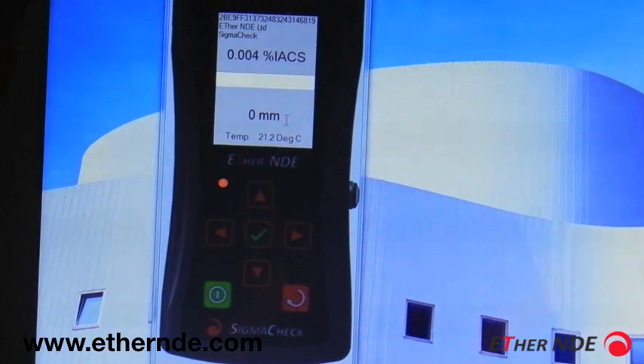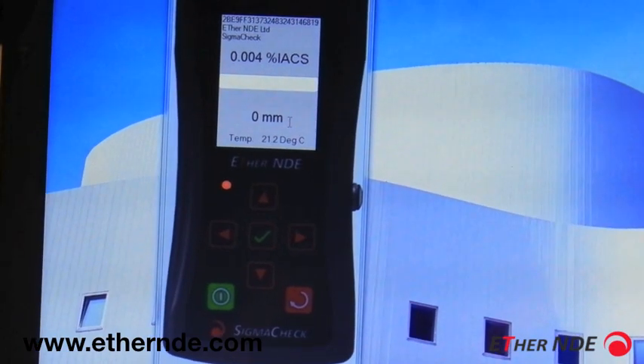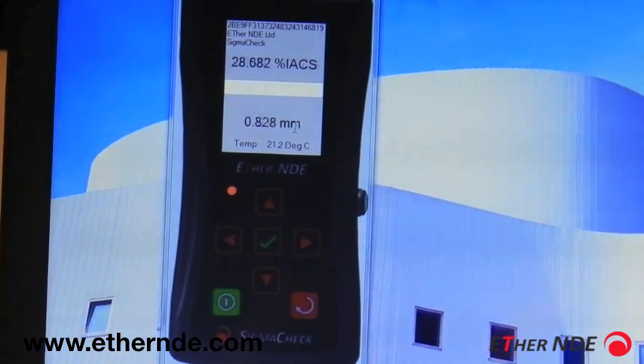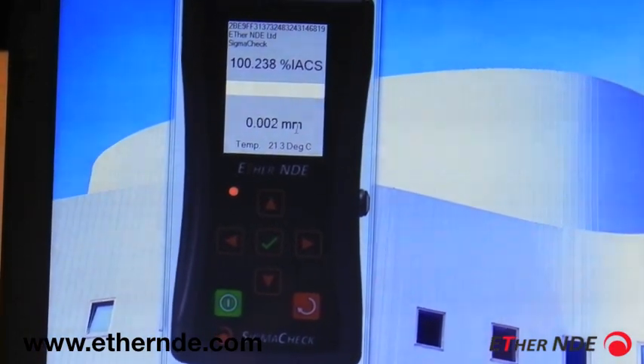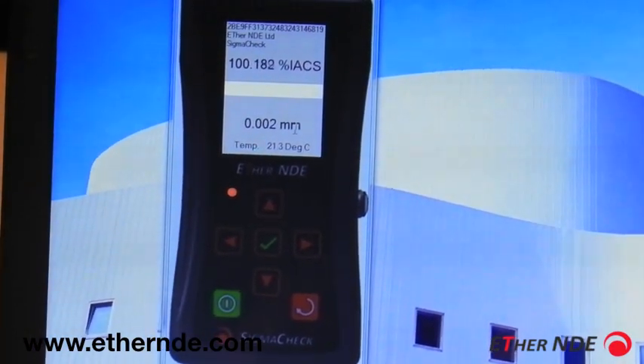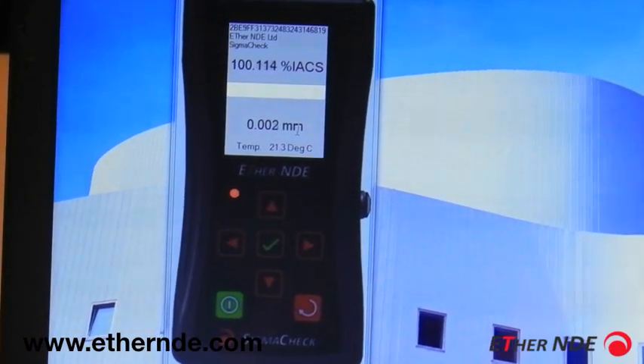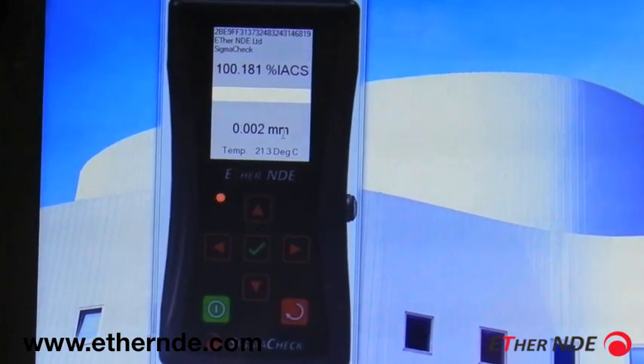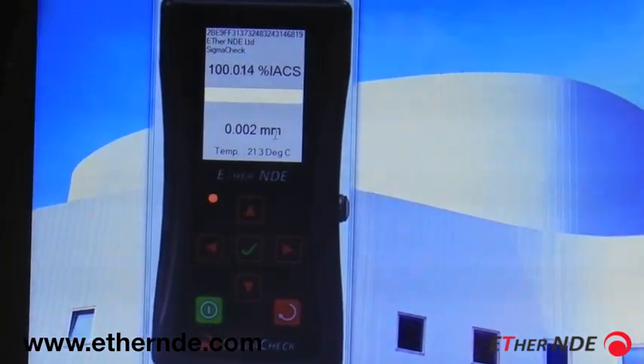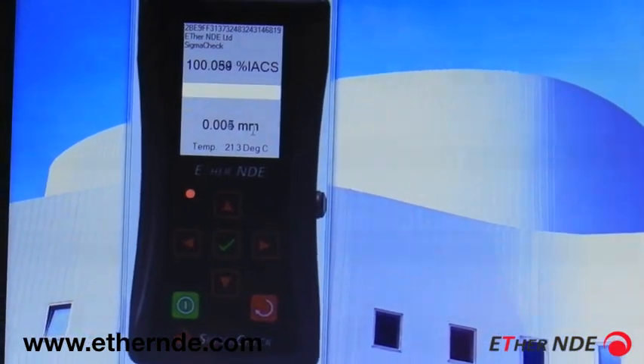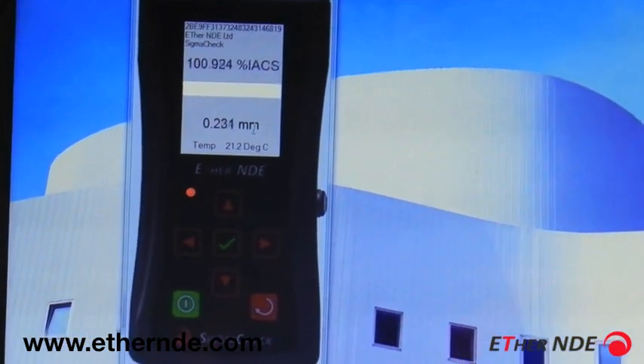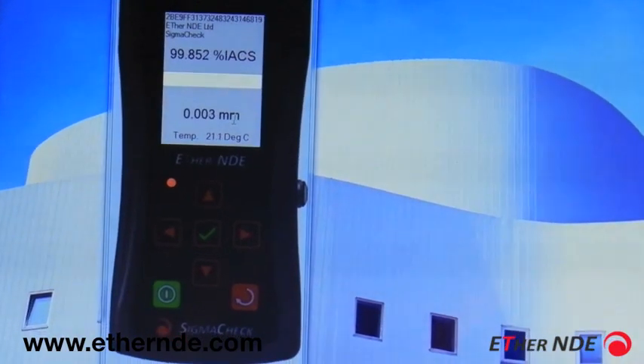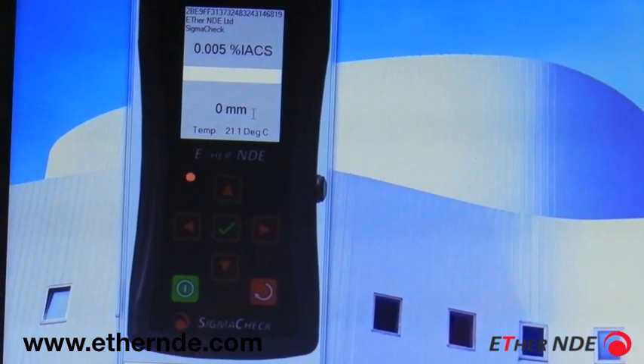Just to demonstrate that very quickly — if I place my probe on a copper block, as you can see it's displaying the temperature and the %IACS. And if I tilt the probe slightly, you can see the lift-off incrementing, all in real time.